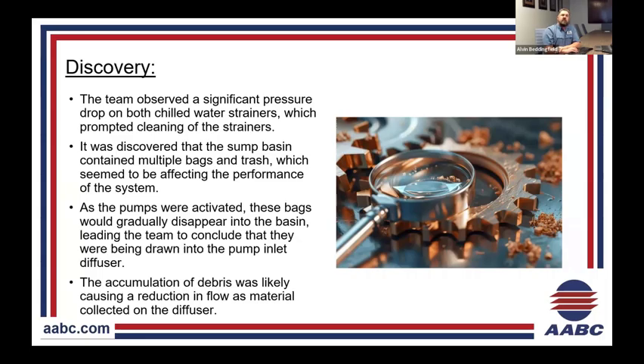But one thing we did notice also was the sump basin contained trash bags. And for us Texans, it's either HEB, Walmart, or some Buc-ee's bags that tend to float around in the sump basin. And we believe that was the primary cause of the flow loss, because we turned off the system again and noticed the bags would float back right to the top of the surface. As soon as we activated the system, the trash bags would eventually start going below the water surface level.